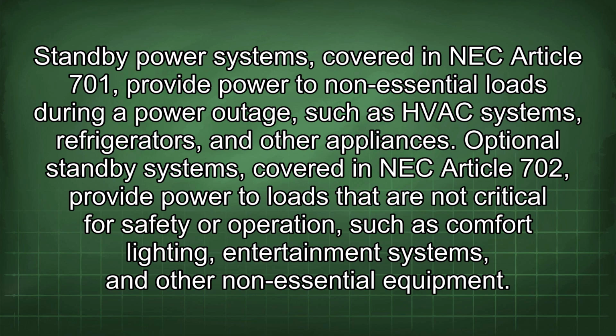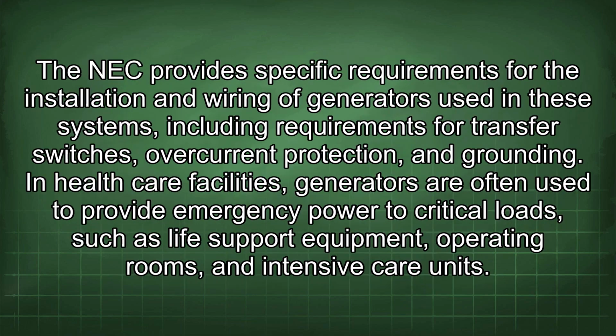Optional standby systems, covered in NEC Article 702, provide power to loads that are not critical for safety or operation, such as comfort lighting, entertainment systems, and other non-essential equipment. The NEC provides specific requirements for the installation and wiring of generators used in these systems, including requirements for transfer switches, overcurrent protection, and grounding.